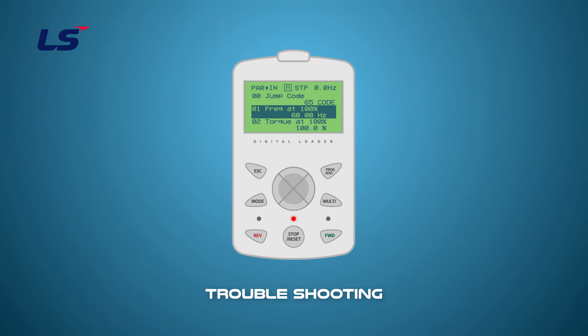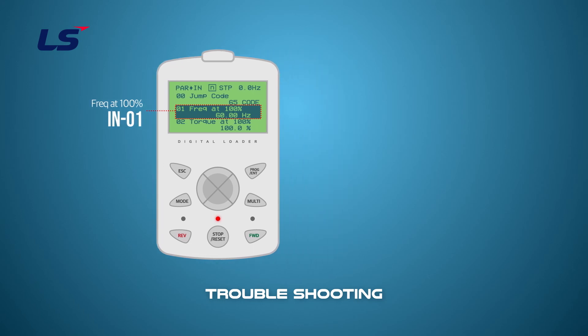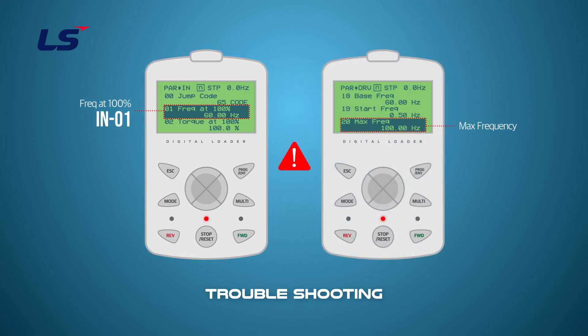The frequency at 100% input can be set in IN group 1 parameter. It does not always work with the maximum frequency, so be sure to check it. If you want to set the maximum frequency to 100 hertz and drive at 100 hertz when the analog input voltage is at its maximum, you must change the IN group 1 parameter to the same value.